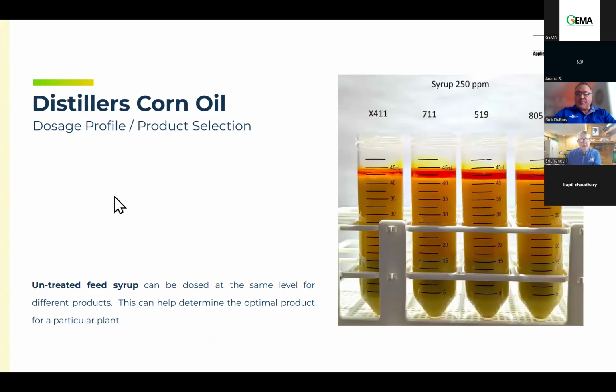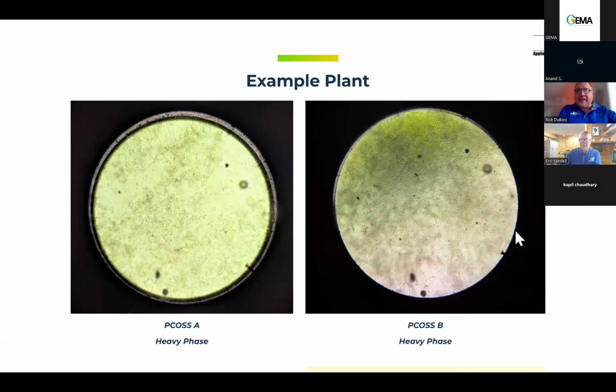Hey, Eric, can I make a real quick point on that? Sure, go ahead. When you're taking samples of the heavy phase, guys, specifically on a disc stack centrifuge, you know how you set your chutes at certain intervals to blow the solids out of that machine and clean it. Typically, around somewhere between 2.5 and 6 minutes.